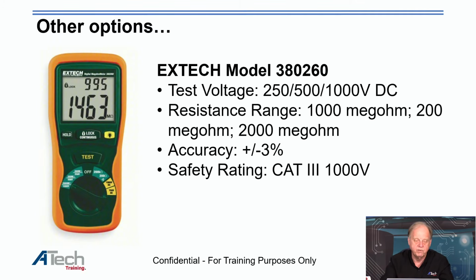Another option is Extech. It does 250, 500, and 1,000 volts DC. The resistance values are 1,000 megohms, 200 megohms, and 2,000 megohms, interesting how they lay it out. Accuracy is plus or minus 3%. This one is rated at 1,000 volts, Cat 3. There are times you'll want to look at a 1,000 Cat 3 rating and times you'll look at a 600, but depending on the circuit you're working on, you want your meter rated at roughly twice the voltage you're measuring.